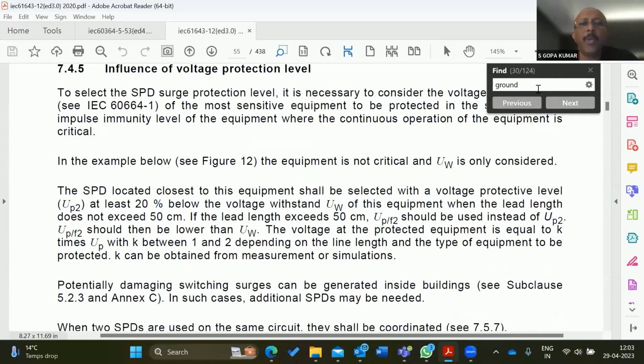The most important point is that an SPD looks like a small component in the electrical installation, but it's a critical component. In most installations, of course, we don't even use SPD. Using SPD is actually a mandatory requirement because it enhances the life of your electrical installation. Without SPD, the transient overvoltages will deteriorate the insulation and the life of the installation will go down. So the question is whether you want a long life for your installation. If you want a long life, of course, you need SPD. And the second is, if you are using an SPD, how safe this SPD should be. So the safety of the SPD, as I said, is very important. Otherwise, this component is going to create a problem in your network.